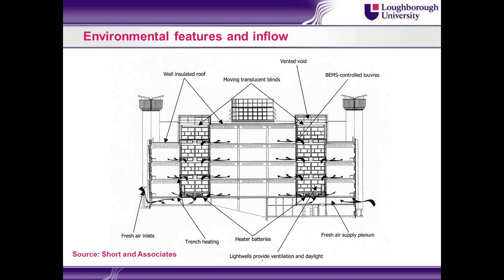Moving translucent blinds at the top of the light wells here, what this does is it protects the inside of the space from direct sun gain. As I said earlier, what we want to do is to provide as much help for the natural ventilation system as possible, so we want to reduce the internal heat gains as much as possible. These blinds enable us to provide daylight, a little bit like the translucent devices up there. They provide daylight, but they reduce the solar gain. We don't want solar gain in these buildings, we want daylight in these buildings. Okay.